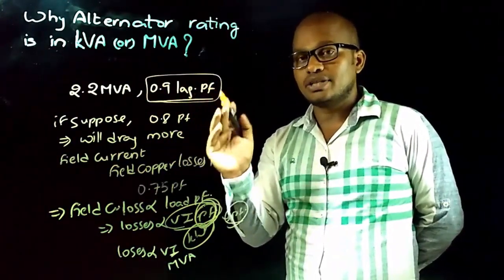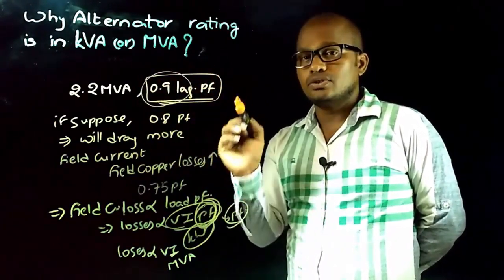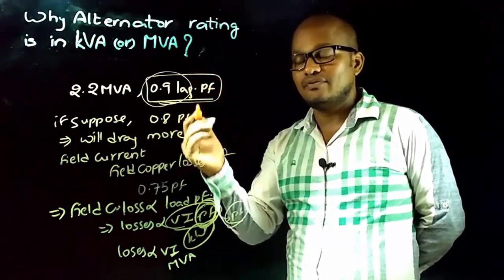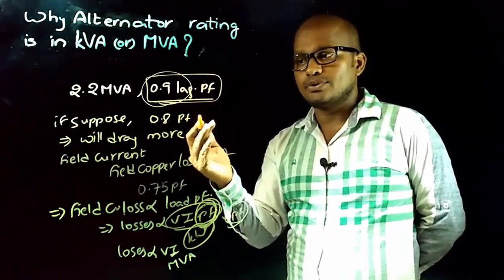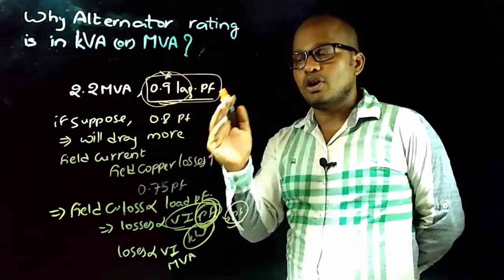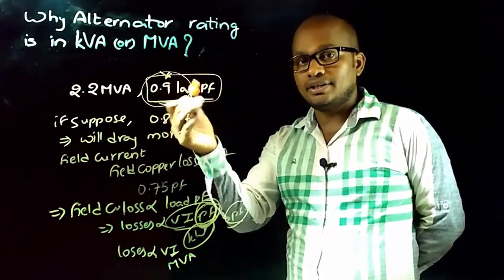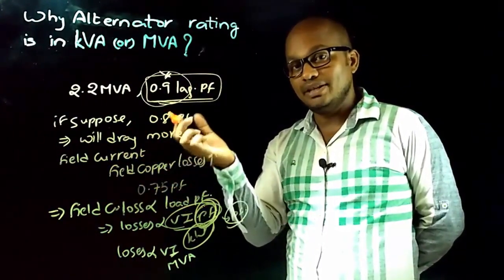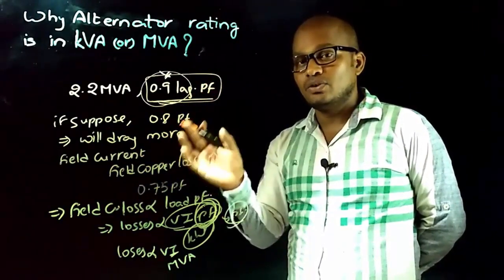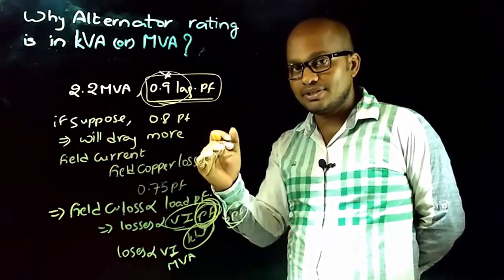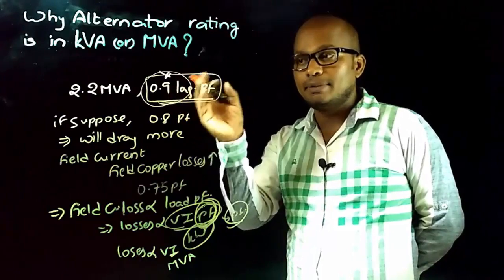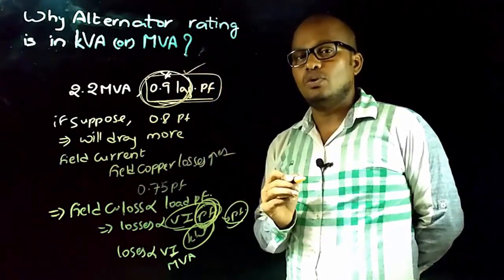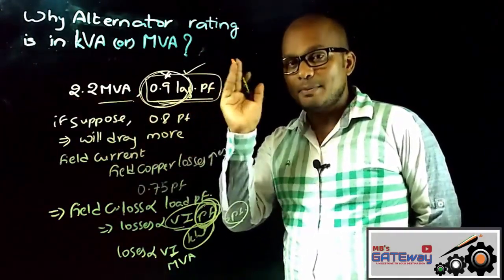Therefore, the rating of the alternator is in MVA when the power factor is fixed. The nameplate details specify that the alternator must be operated at a particular load power factor at rated load, so heating in the machine stays within limits. If the designer did not specify the load power factor, the operator might operate at different power factors, causing the alternator to draw more field current, increasing copper losses and heating enormously, which might damage the alternator.